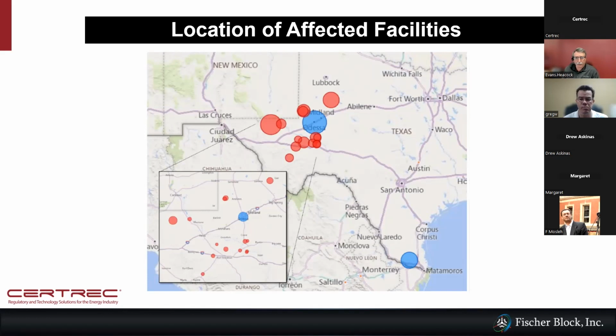There was some instability on those phase lock issues. So there's a number of items that cause these inverters to trip, and they're still working through all those items. But you can see it was pretty large scale and not necessarily right up next to where the fault occurred itself. The Odessa, mainly the Odessa areas, but then definitely a few way down south. So with electricity, nothing's necessarily localized. When you have an issue on a grid, it can ring out further than just the local area itself.